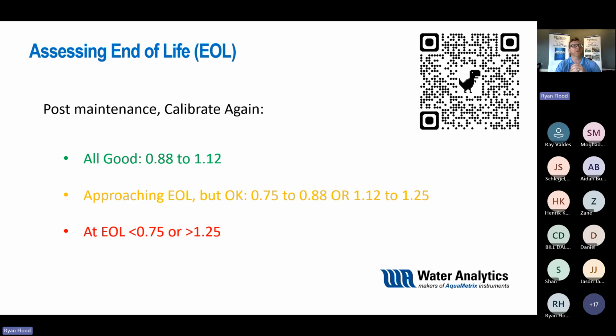So you've already gone through the calibration process and you identified that your slope was off and your efficiency was off. And again, looking at these numbers, it's the slope of pH to pH versus the millivolt to pH slope that's read there, or looking at this as your efficiency. So again, if after you've performed your maintenance you're back into that 88% to 112% range, you're good to go. That sensor is ready to perform, and you will get all the right readings you want to get, and your sensor can continue to perform for a long period of time after that.